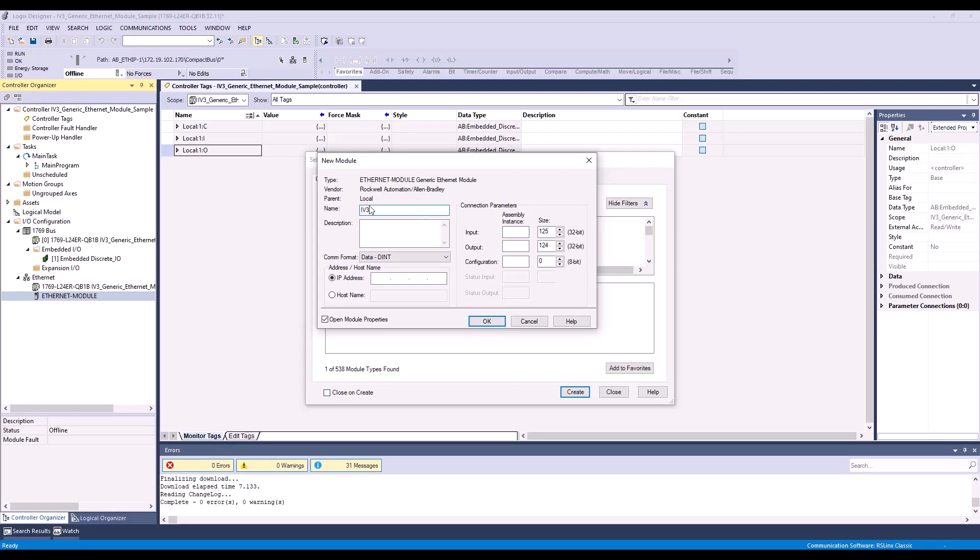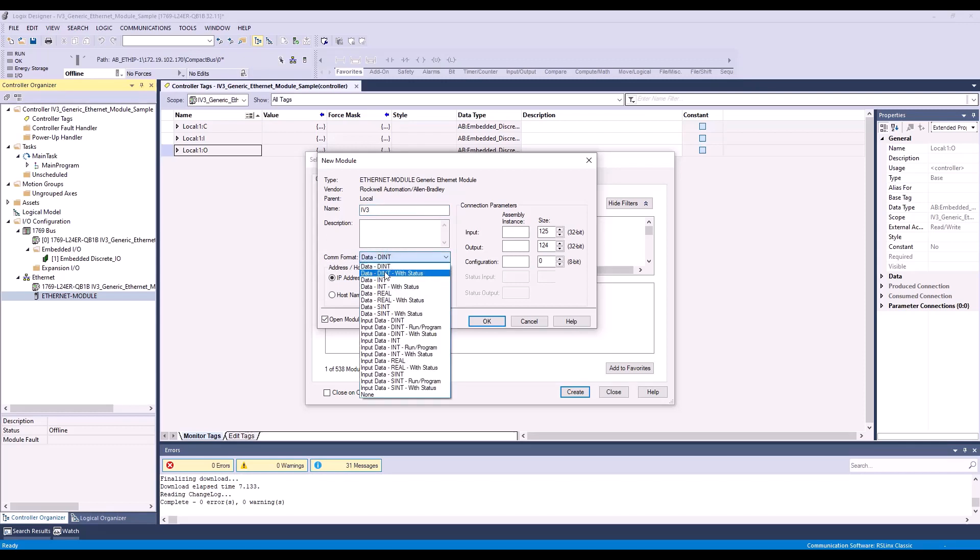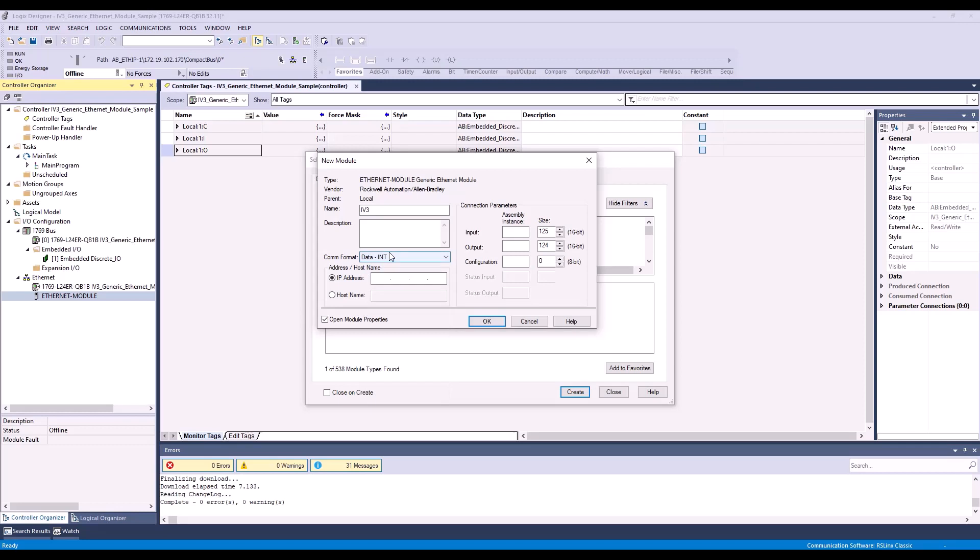And notice that this name does need to match the tag file that I import later on in this video. Next, I'm going to change the format to data-int. We do recommend using the integer format for the IV3 as it sends its data as 16-bit. Then we need to type in the IP address for the IV3. My IP address is 172.19.102.248.